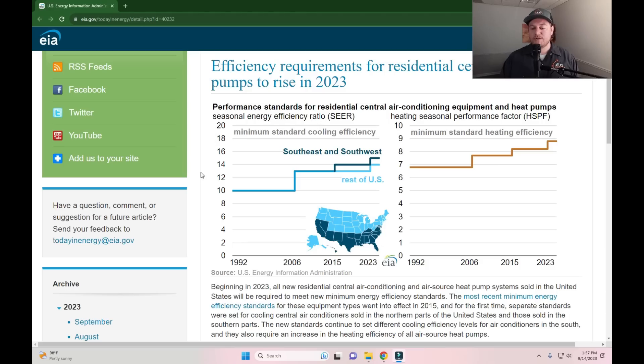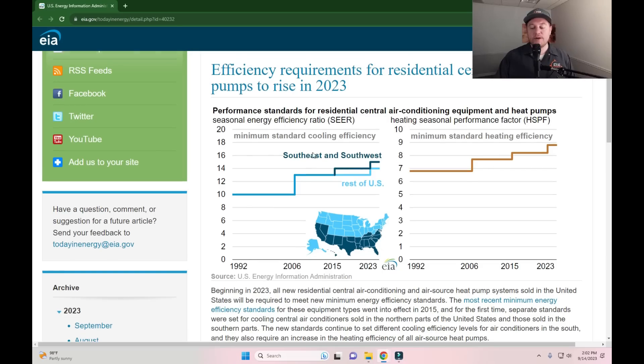If we look at this chart, it shows the minimum efficiency standards for heat pump and air conditioning systems. Since I'm located in Texas, I'm going to be focusing on the southern region — please note that the northern region does have slightly different requirements. The Department of Energy has been increasing the minimum SEER requirements for a while now. In 2006, they went from 10 SEER all the way up to 13 SEER. Fast forward to 2015, there was another jump from 13 to 14 SEER. And in 2023, there was another jump from 14 to 15 SEER.